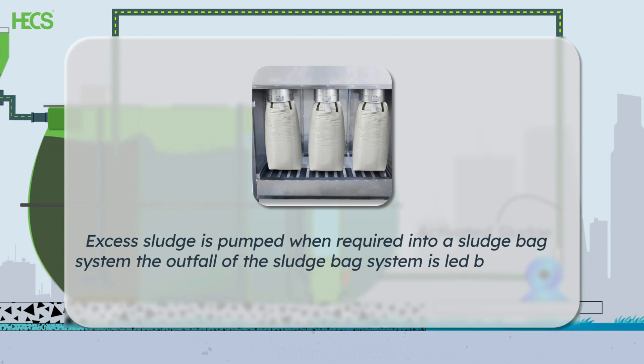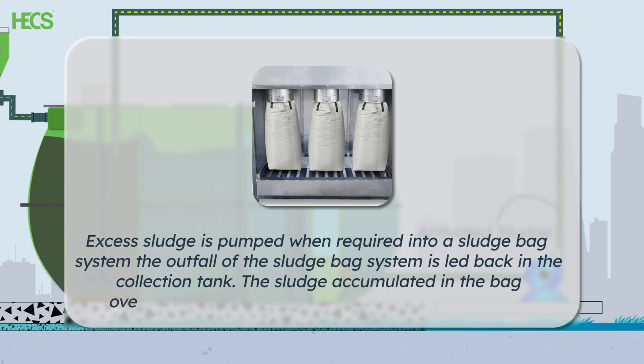Excess sludge from the MBR tank is pumped when required into a sludge bag system. The outfall of the sludge bag system is led back into the collection tank. The sludge accumulated in the bag over time is dried to form dried cakes and disposed.